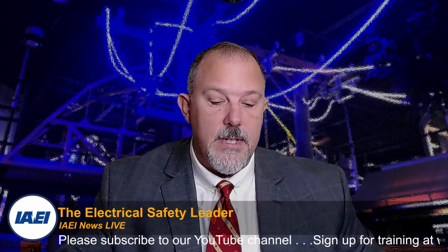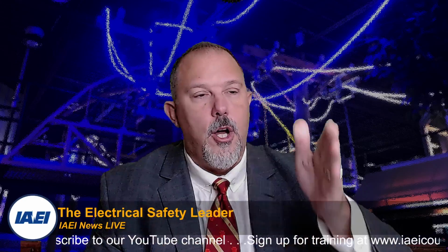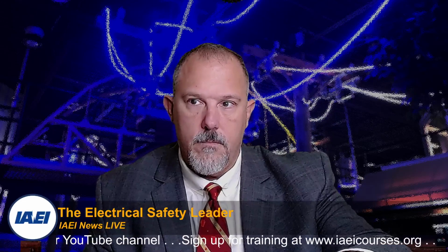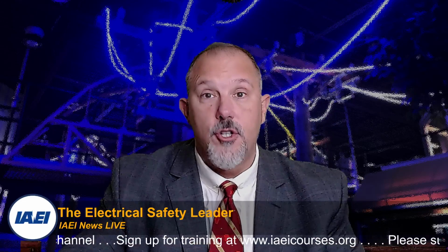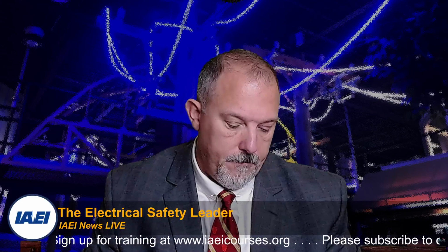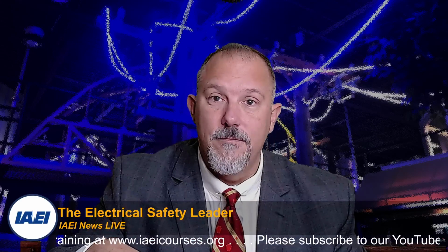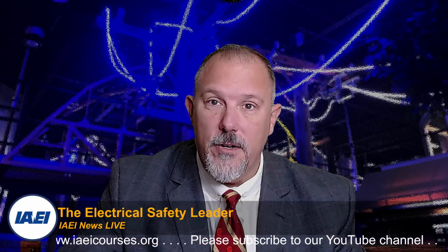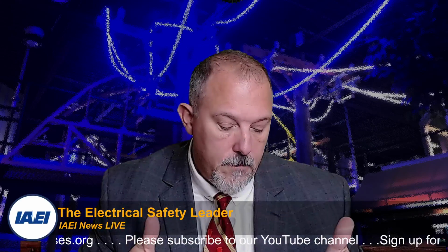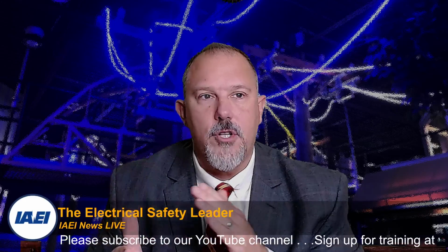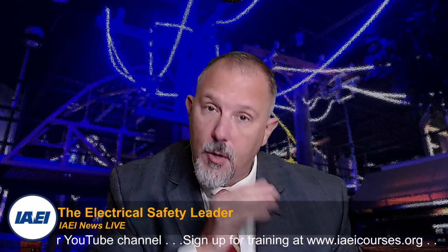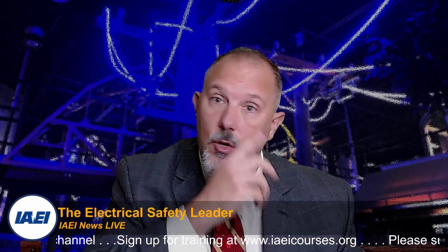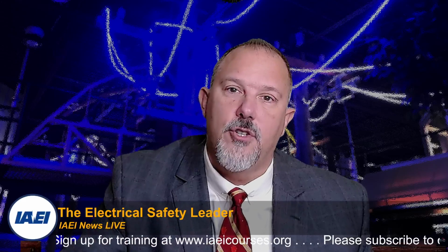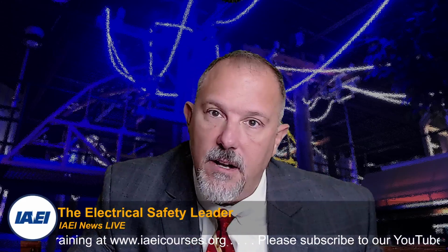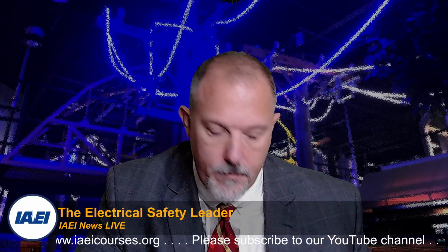Now, let's talk about those three. An overload is not a fault current. A short circuit is a fault current. A ground fault is a fault current. It's got the word fault in it. So the difference between a fault current and an overload: they're both overcurrents, right? They're both overcurrents because they're all in that definition. We know these current values are going to exceed the rating of conductors or other equipment.